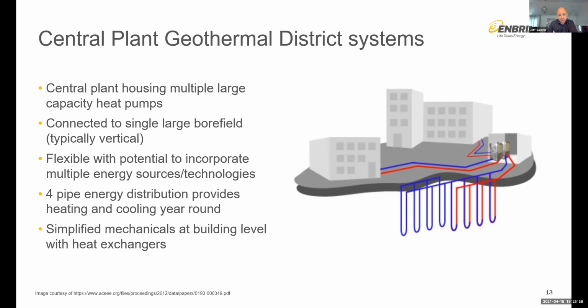We're delivering usable thermal energy either in tempered water or chilled water, and a simple heat exchanger in the building is all that's required, typically a water-to-water heat exchanger. So the district energy heating loop would pass through one side of the heat exchanger, and the building energy loop would be tied to the other side, and the heat would simply be transferred into that building and distributed amongst the various floors of that building or throughout the building to the fan coil units or potentially additional heat pumps or floor radiant systems, depending on how it's set up.